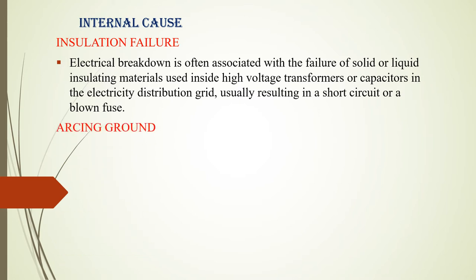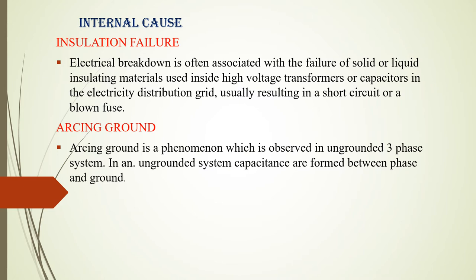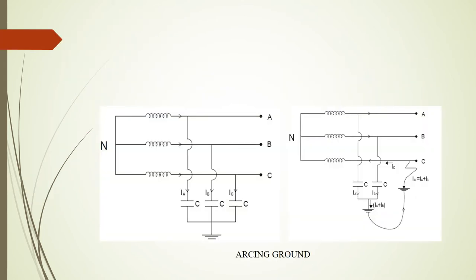The next important concept is arcing ground. Arcing ground is an electrical phenomenon that usually occurs in an ungrounded three-phase system — that is, a system where the neutral point is not connected to earth. When the neutral point is not connected to earth, this phenomenon takes place and is one of the major causes of transients. You can see in the diagram on the left-hand side a three-phase balanced system with a neutral end that is not connected to earth. There will be capacitance existing between each phase with respect to ground.